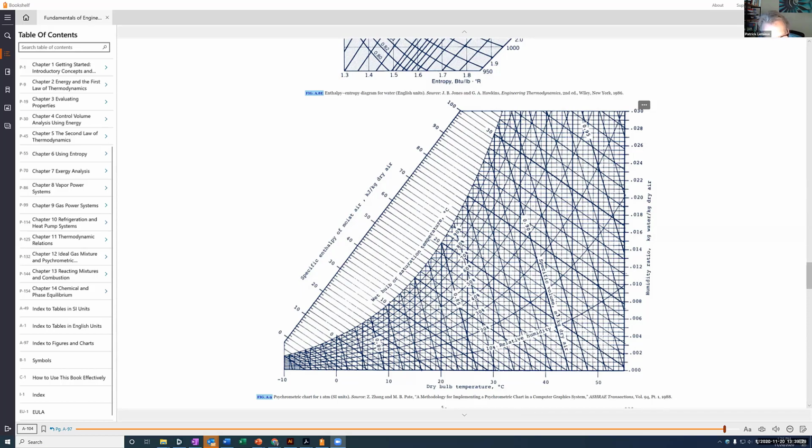So I'm on this one. That looks like 14 degrees Celsius, my wet bulb temperature. So even though the air is at 20, if I had a sling psychrometer like we saw before, I would expect the one with the wet gauze on it to read 14 degrees Celsius, is what we've established there. Okay, all right, I think I got all I'm going to get out of that chart.